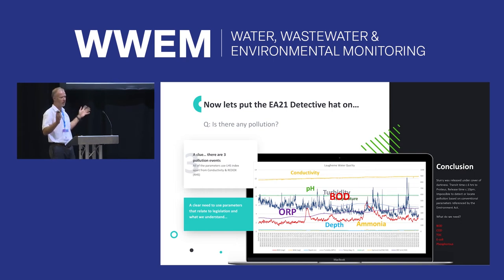There are three events that are going to happen here, over about 5 or 6 days. All the parameters go down the left-hand axis, apart from conductivity and redox, which go on the right. So we'll put turbidity up. It's a little bit spiky because it's pretty low level, running between about 4 and 8 NTU.